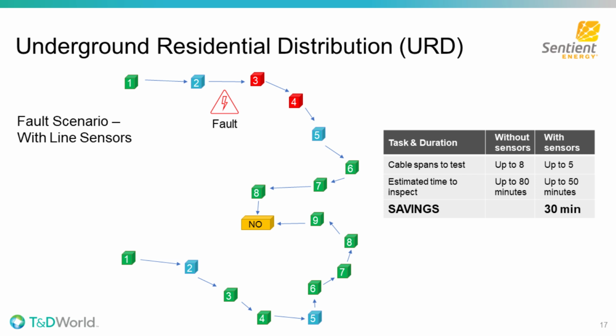Absolutely correct. We monitor both the primary and secondary side on the transformer. Some of the use cases we have operationalized as of today are, number one, tracking for detrimental loading of transformers to then make replacement planning a data-driven approach instead of reacting to failures. And with very long lead times for transformers these days, this has been found to be a fairly useful tool for several utilities.